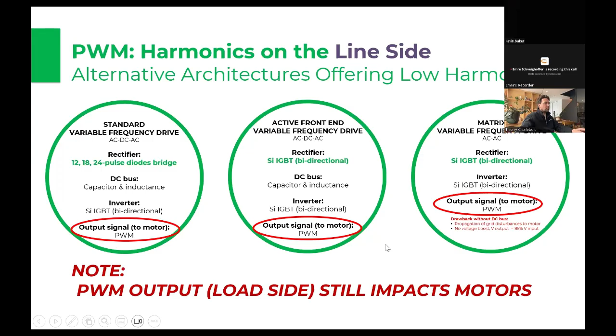Now let's talk about the load side. So we just finished talking about the input side. Let's talk about the output side of the VFD. We have a square wave trying to pretend to be a sine wave, and that causes a lot of issues to the cable and the motors. So you have voltage spikes, corona discharge in the cable, which can break down the cable insulation. These voltage spikes can break down the motor insulation. That shortens the motor life.